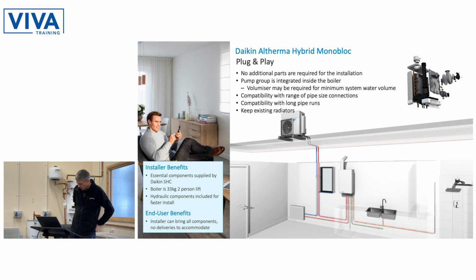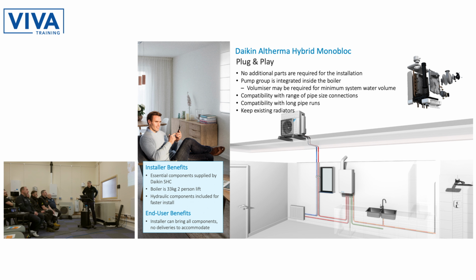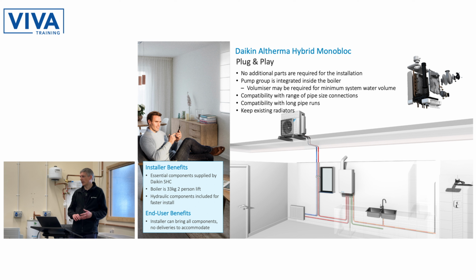And one of the big bonuses or features of this particular equipment is that you can keep the existing radiators. I'll come to it in a minute, but using the boiler, you can get the temperature up to 80 degrees. So that should be compatible with any heating system. Obviously, you don't really want to run it at 80 if you can help it. You want to be running it lower than that for best efficiency, but it will deal with whatever heating system is already in the property.